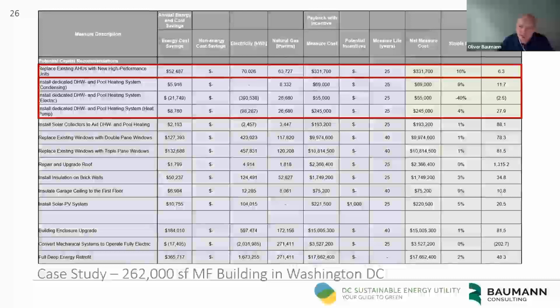Since the client indicated they want to electrify their buildings and eventually go carbon neutral, we also analyzed direct electric heating for the pool and domestic hot water system. Here the energy cost savings are actually negative, so we increase utility costs, due to the switch from natural gas to electricity, which is more expensive. We have a relatively low net measure cost of $55,000, but the simple payback doesn't exist, and there's no simple ROI.